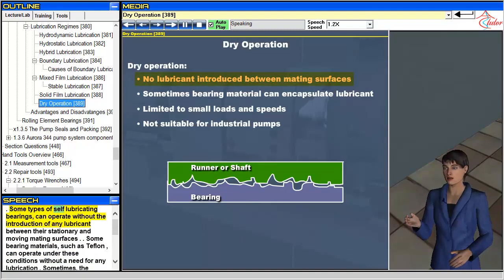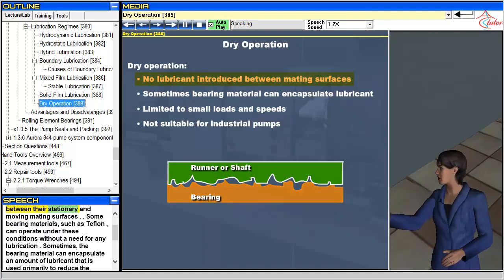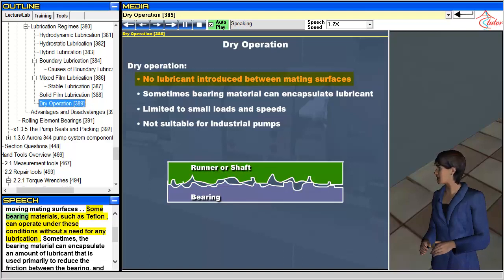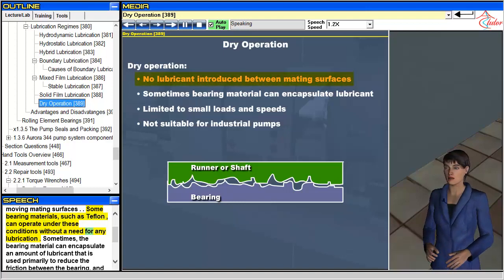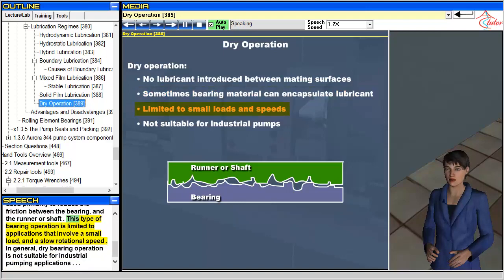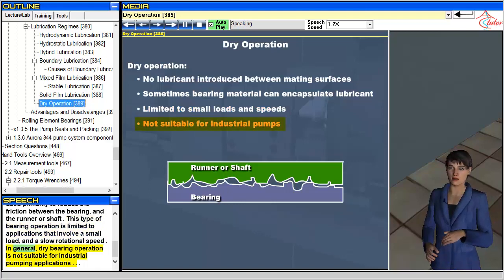Some types of self-lubricating bearings can operate without the introduction of any lubricant between their stationary and moving mating surfaces. Some bearing materials, such as Teflon, can operate under these conditions without any lubrication. Sometimes the bearing material can encapsulate an amount of lubricant used primarily to reduce friction between the bearing and the runner or shaft. This type of bearing operation is limited to applications involving small loads and slow rotational speeds. In general, dry bearing operation is not suitable for industrial pumping applications.